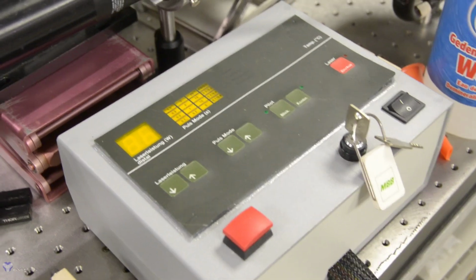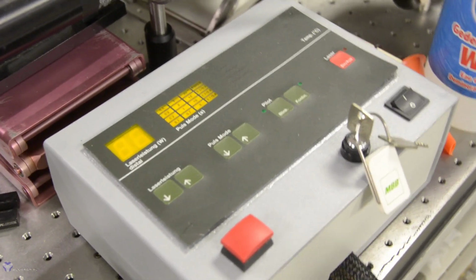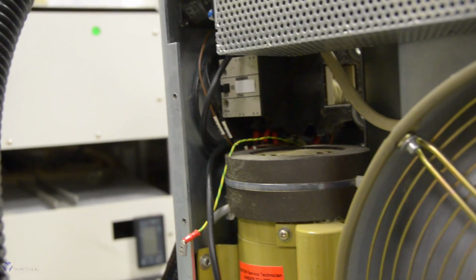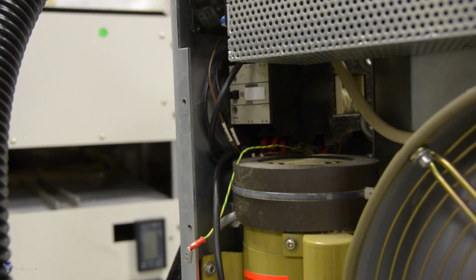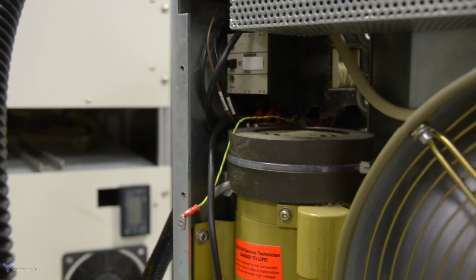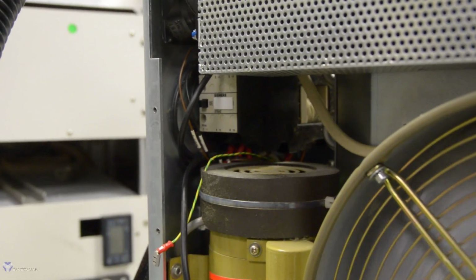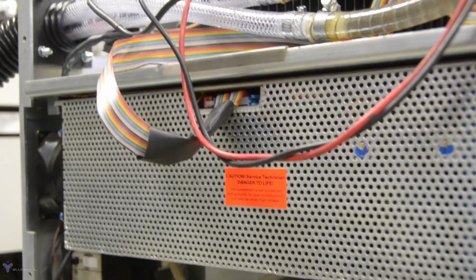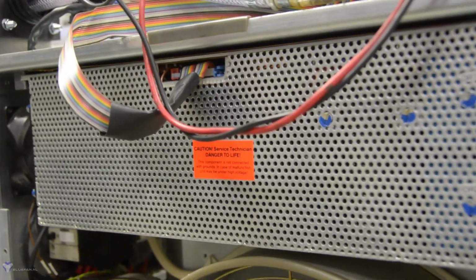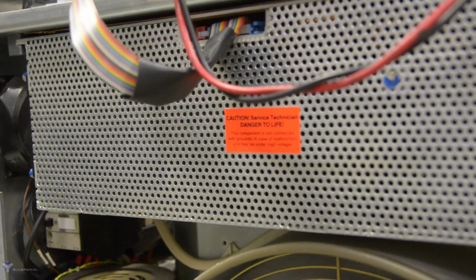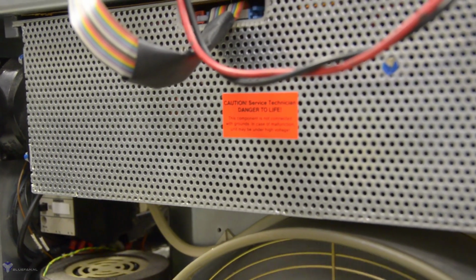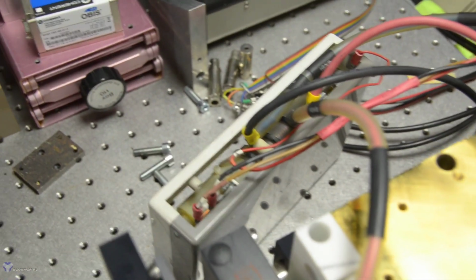I found at least one error that I made. I'll show you my thought process. So when I turn on the laser, the pump starts, and above the pump the contactor enables and immediately disables. You see the black pin jumps in and then pops out again. Now what is connected behind that contactor is the lamp power supply. So I was thinking, what if the lamp, for example, doesn't ignite, and then the power supply turns on, there's no ignition, and it turns off. So I was measuring the lamp voltage when I was looking at the head, and then I noticed I wired up the starter wrong.